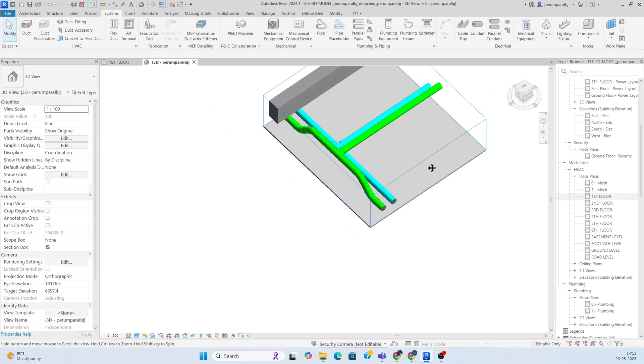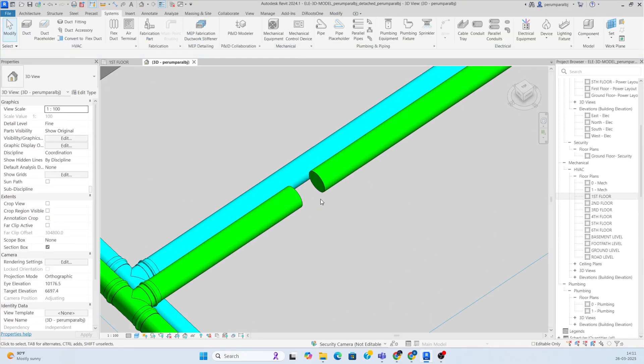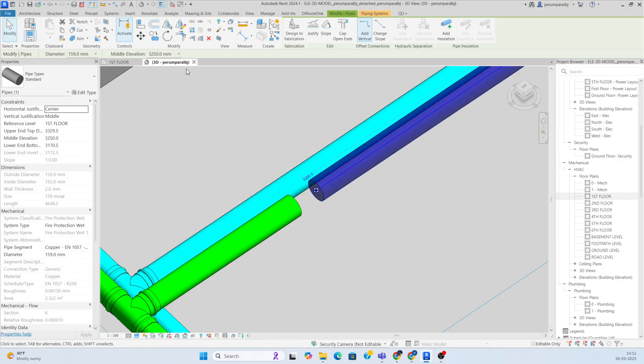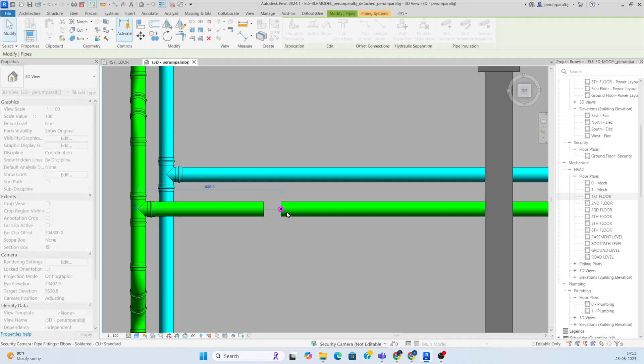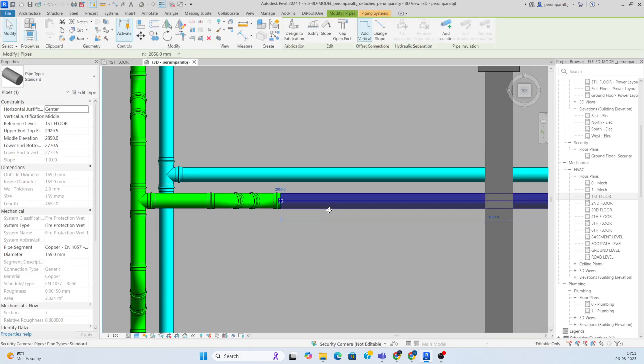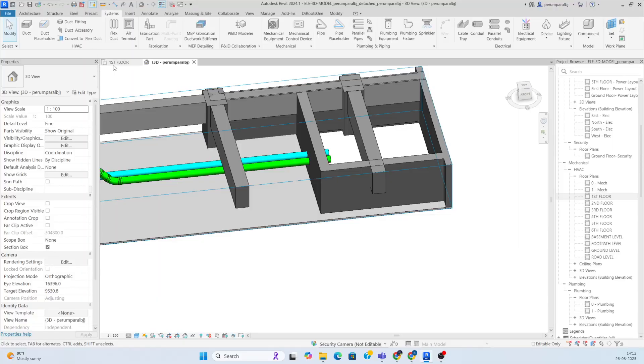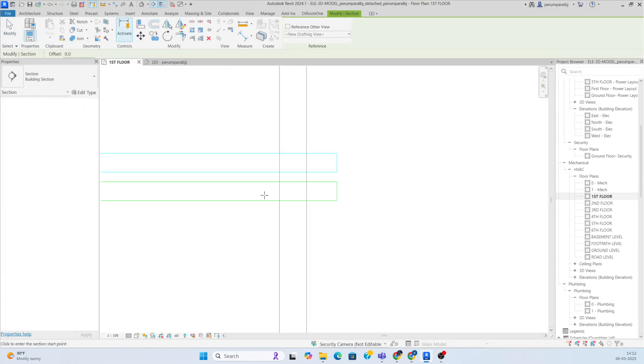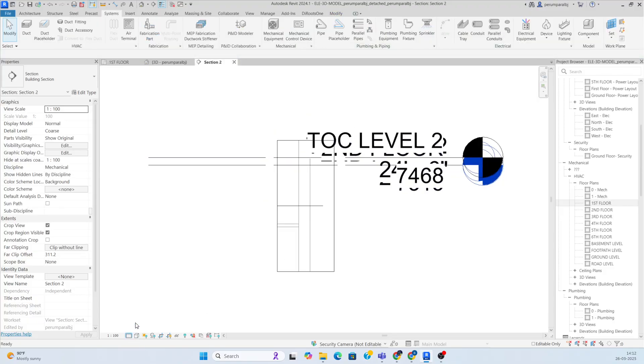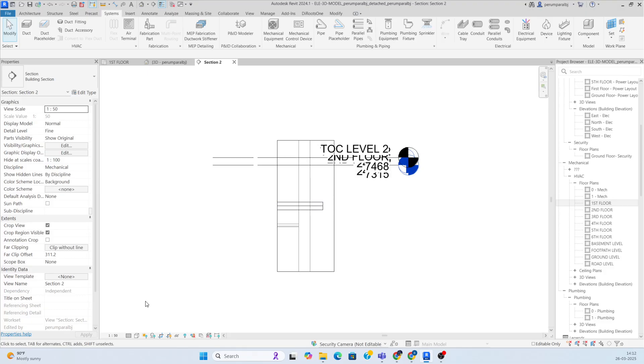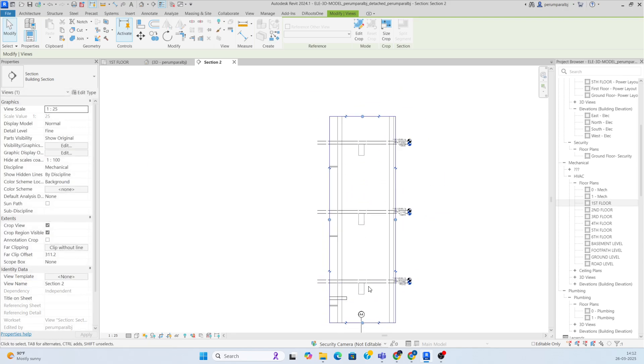This is how you handle pipe fittings and connections. The pipes need to be at the same level in some areas, so split and adjust elevations as required, then connect them together. You can also make a riser — go to View, create a section, set the scale to 1:25, and from the section view you can draw the pipe going upward.